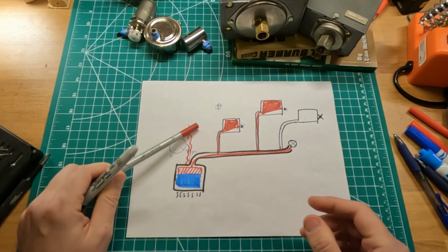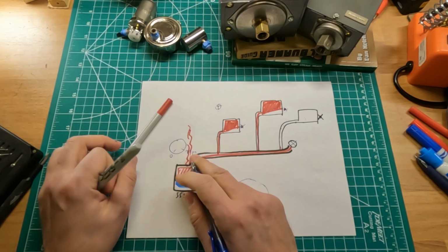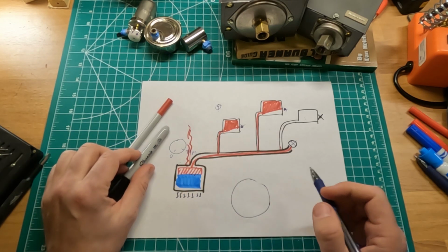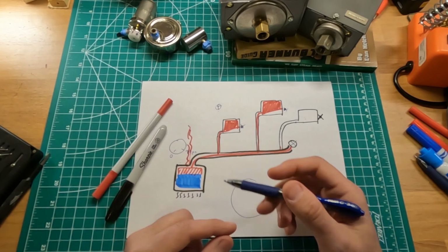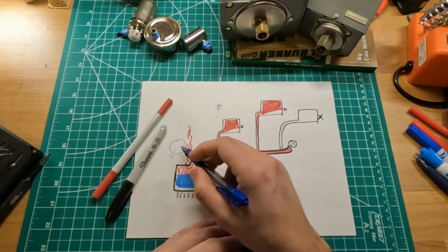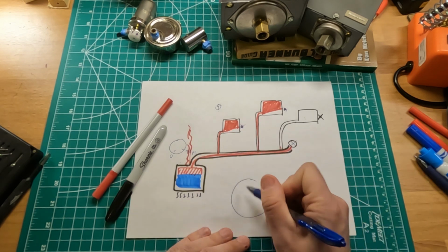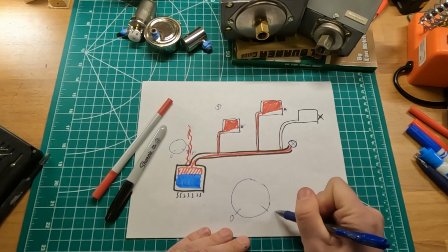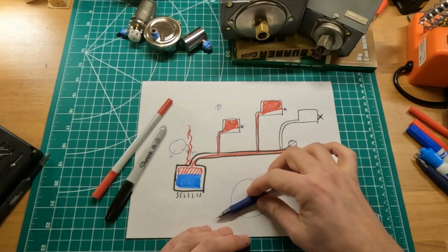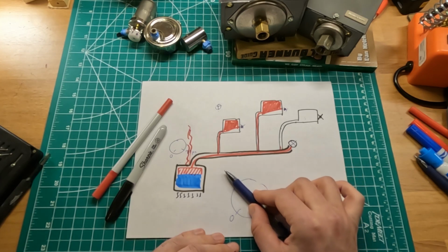So for instance, let's say you have a pressure gauge. Now again, the 0 to 30 pressure gauge is mandated by the code, so all manufacturers put it on their boilers, because you're operating with such a small level of pressure, usually half to maybe 2 pounds of pressure maximum. So this 0 to 30 gauge barely registers anything. However, if you have a secondary pressure gauge, for instance, from 0 to 5 psi, then all of a sudden you might discover that your pressure rises at a certain speed. And again, I'm right now exaggerating the speed of the rise. It's probably rising much slower than that.